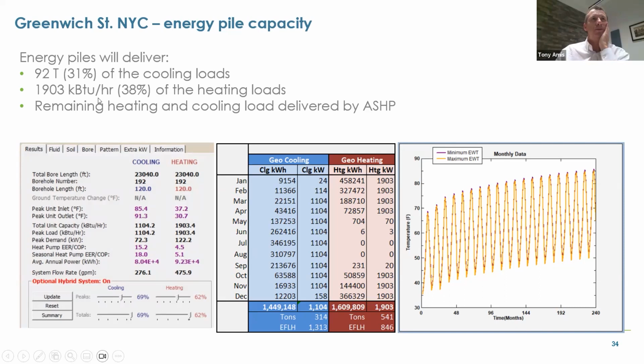We know we've only got 192 loops in this particular project - that's 3 loops and 63 piles. The design here is telling us that we can deliver 31% of the cooling to this building and 38% of the heating load. But what's really important is to understand what happens over time.